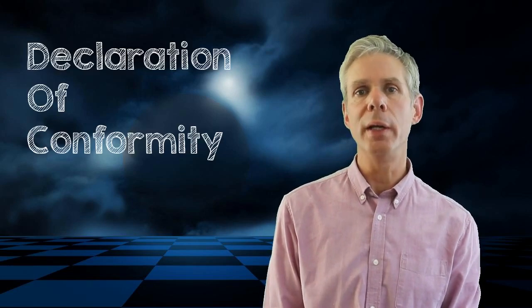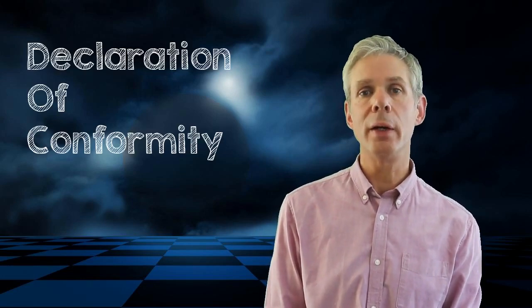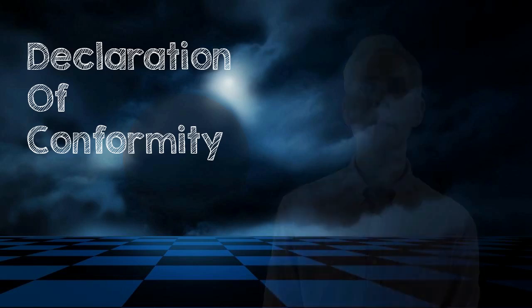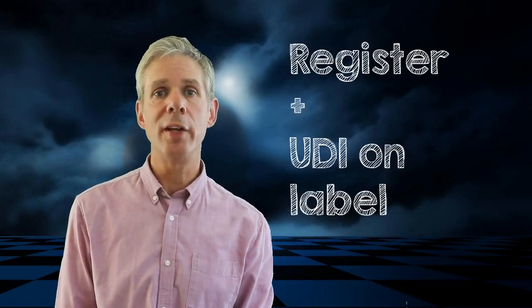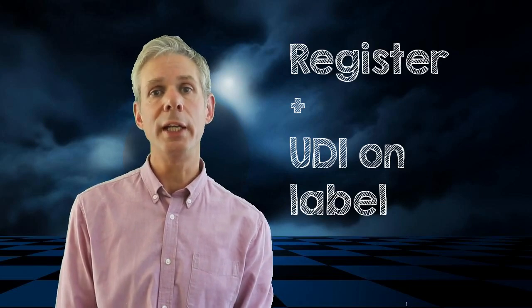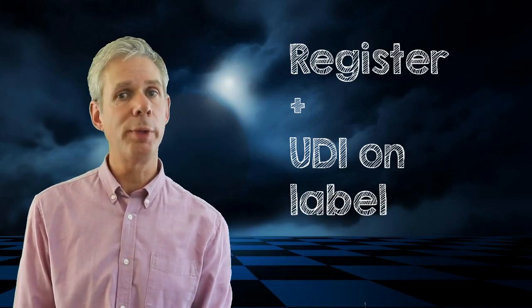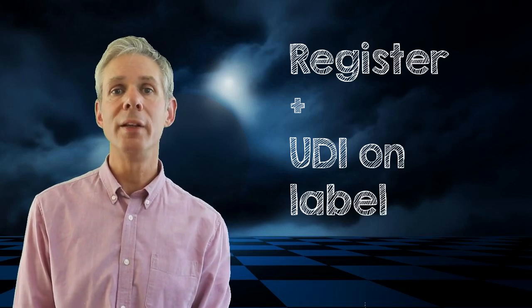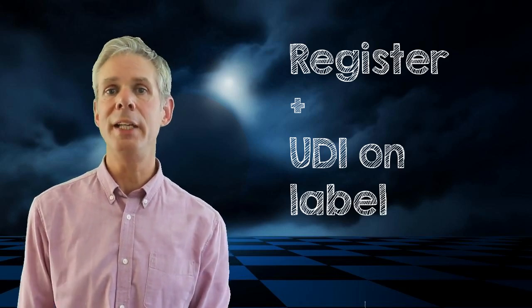5. Now you can sign your Declaration of Conformity, which says that you comply with the MDR. This is essential. 6. You'll need to register your medical device and its UDI with the EU. Remember, the UDI must be on your device label. Now you can market your device in the EU.